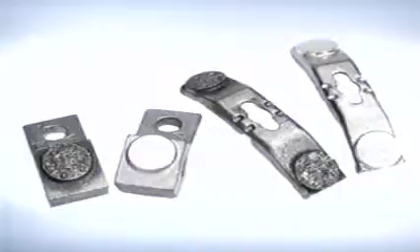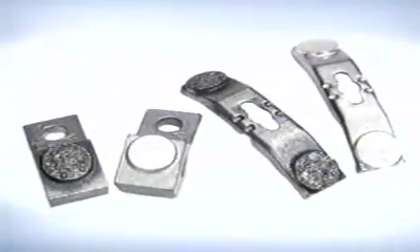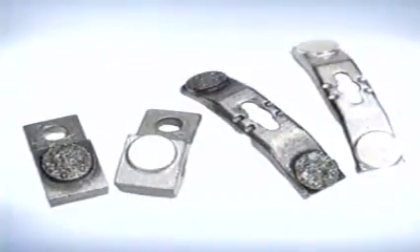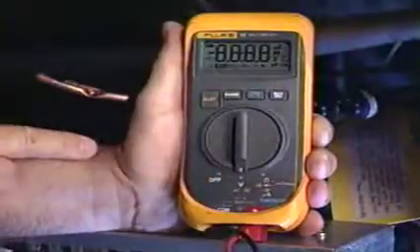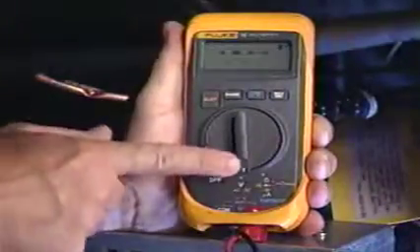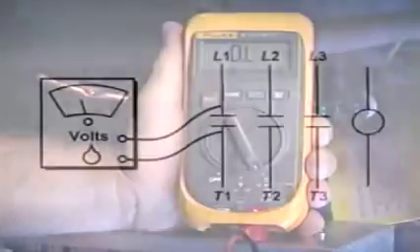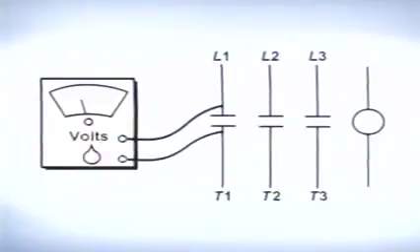The contactor contacts should be smooth. A visual inspection can be done to check the condition of the contacts. Contacts can also be checked with either a voltmeter or an ohmmeter. When checking the contacts with a voltmeter, the test leads of the meter should be placed across the contacts, as shown here.